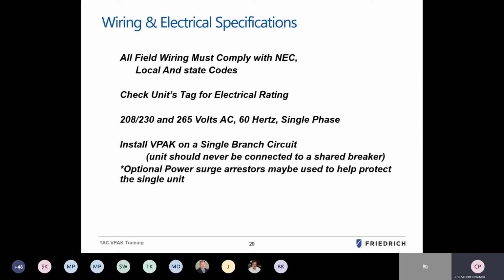Make sure that you always check the unit's tag for the electrical rating, making sure that you're not putting a 208 volt or 230 volt unit in place of a 265 volt, and vice versa, and making sure that you are working with single phase voltage and not three-phase voltage. And then install a single branch unit. The unit should never be connected on a shared breaker. Obviously, these are electrical supplied air conditioning package units, which do have electric heaters in them. And in the wintertime, they will draw power and excessive amperage that if they are shared, you will trip breakers or create other electrical issues.